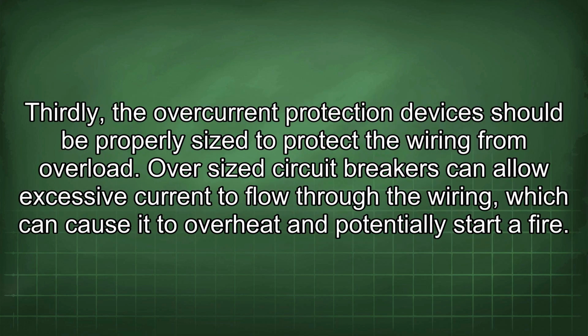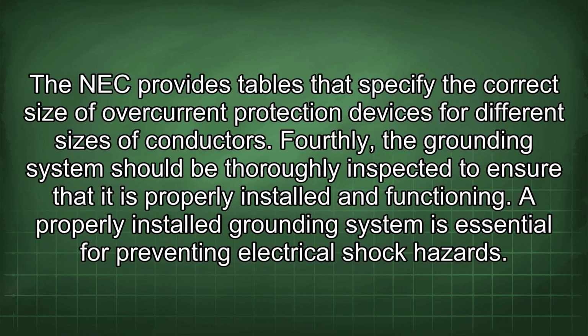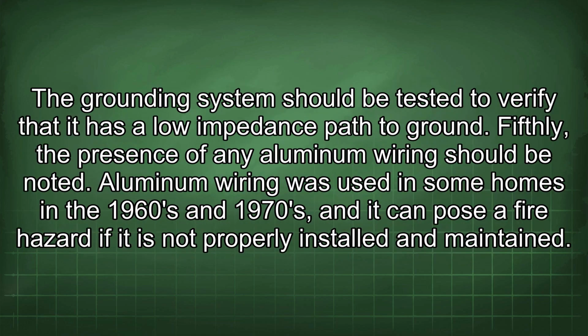Thirdly, the overcurrent protection devices should be properly sized to protect the wiring from overload. Oversized circuit breakers can allow excessive current to flow through the wiring, which can cause it to overheat and potentially start a fire. The NEC provides tables that specify the correct size of overcurrent protection devices for different sizes of conductors. Fourthly, the grounding system should be thoroughly inspected to ensure that it is properly installed and functioning. A properly installed grounding system is essential for preventing electrical shock hazards. The grounding system should be tested to verify that it has a low impedance path to ground.